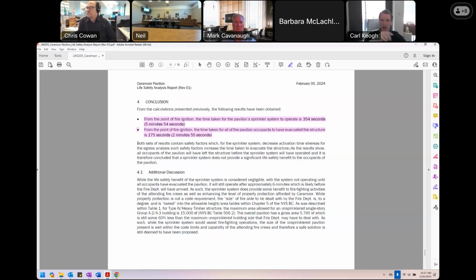And then the final bit on this section 4.1 on page 17 states that, obviously, we've demonstrated that the provision of the sprinkler system doesn't provide any additional benefit to the occupants of the pavilion, because they're all out of it by the time it activates. However, the fire department are on their way at this point, and they will not have reached the pavilion within 6 minutes. So were a fire to occur, the sprinklers would activate, everybody's out, but the fire department haven't yet arrived. So obviously having a sprinkler system within a building is advantageous from a firefighting perspective.